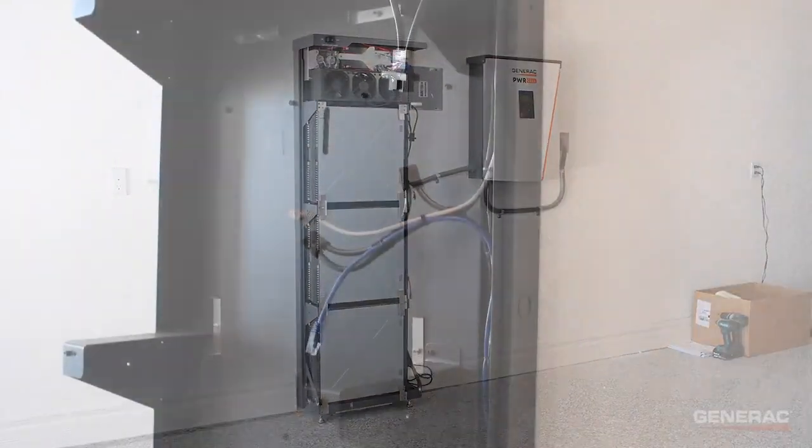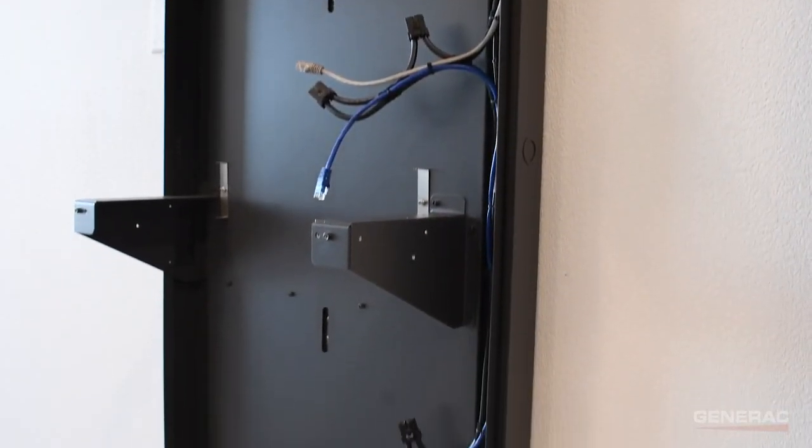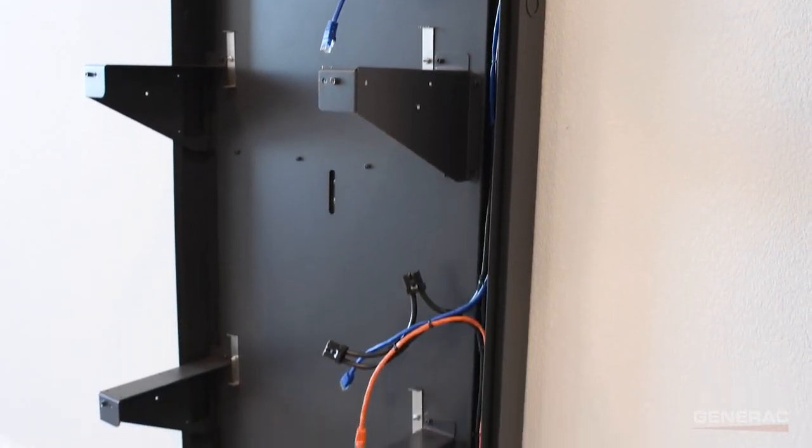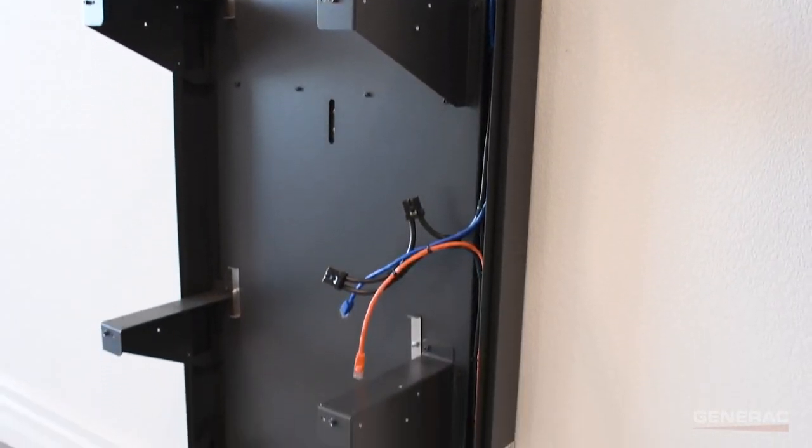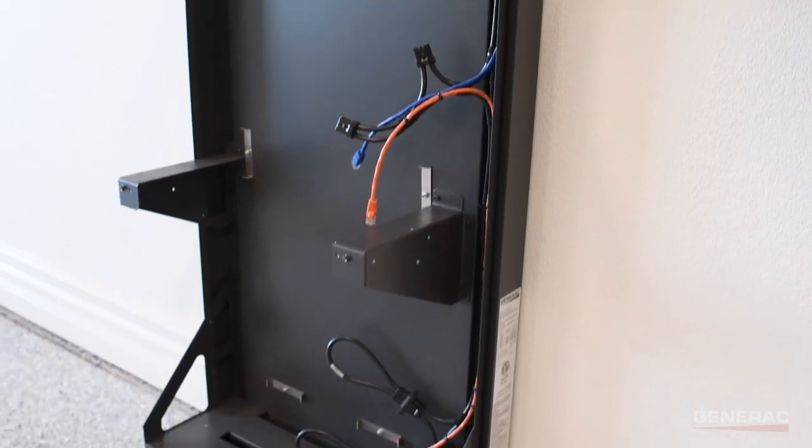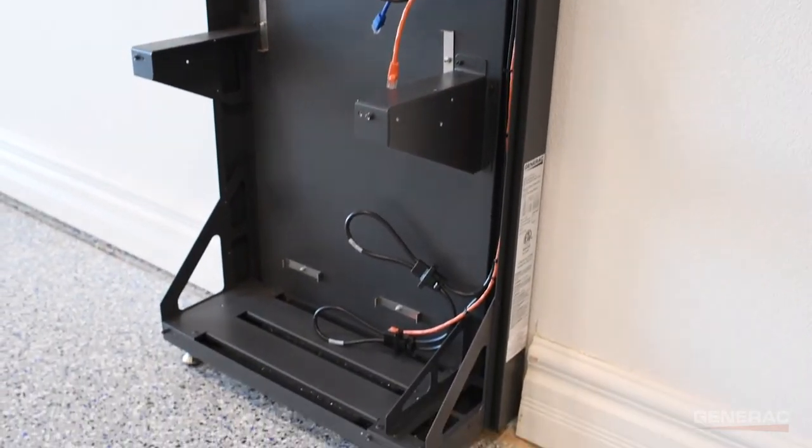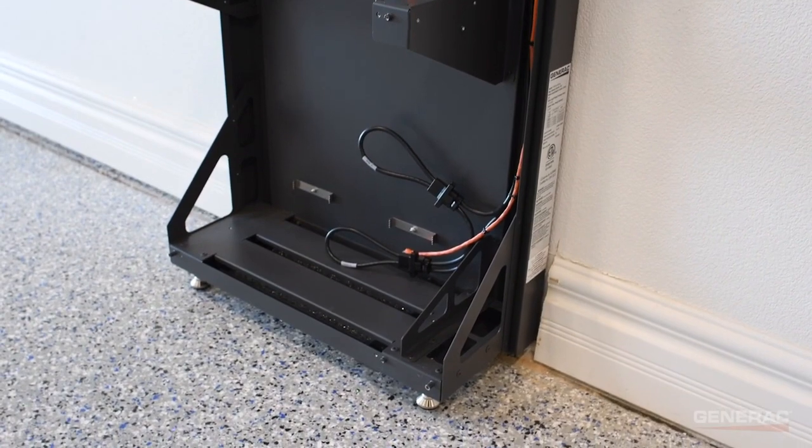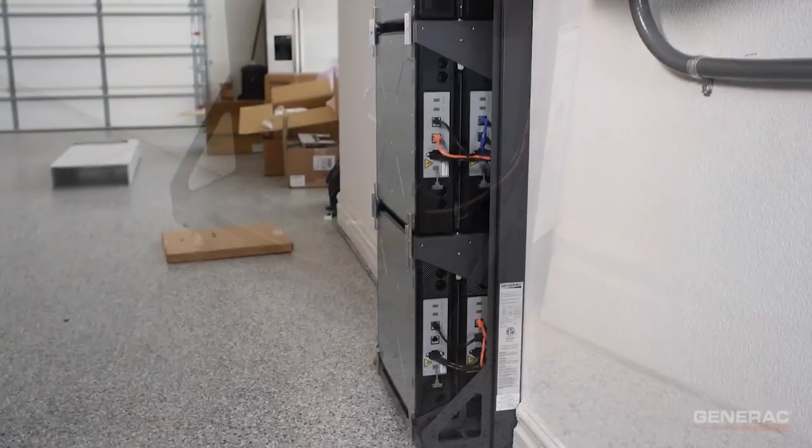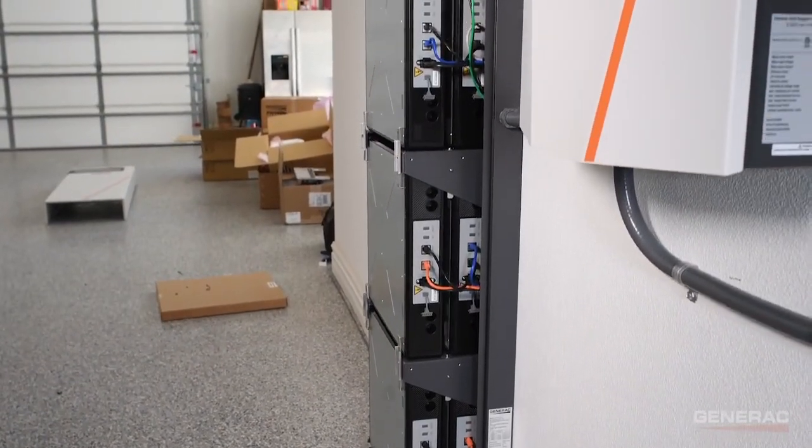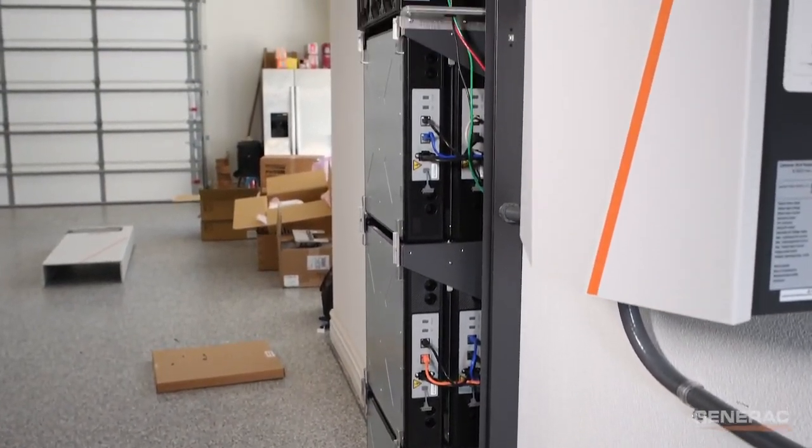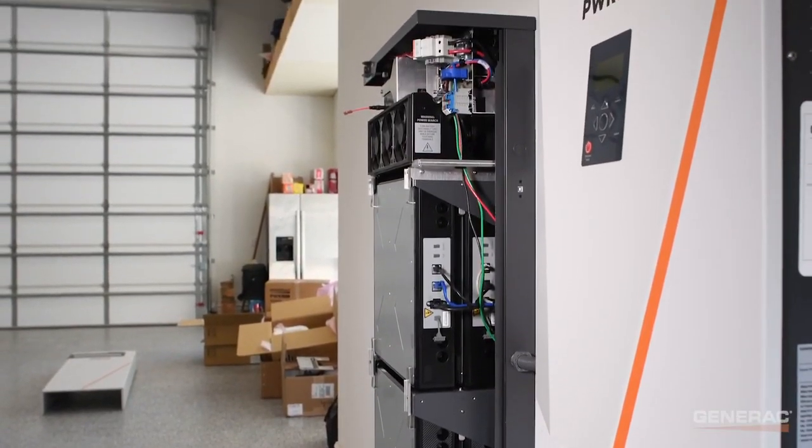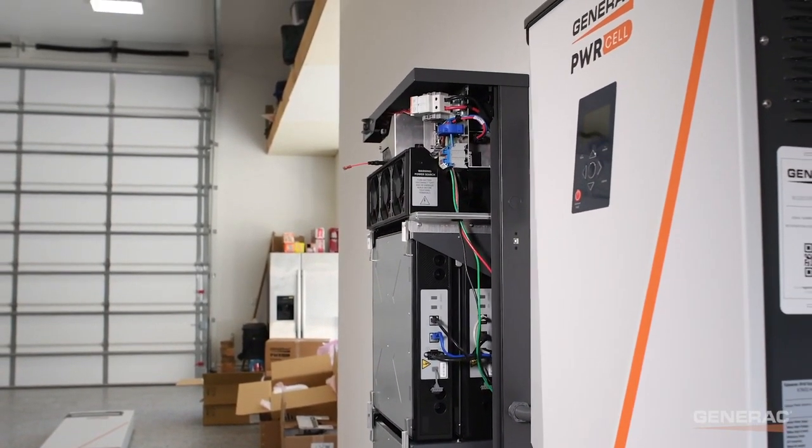Locate the battery's power cable harness. It's built into the battery cabinet and runs down the right side of the cabinet alongside the battery modules. It includes touch-safe power connectors that connect all battery modules in a series circuit to the BMU for charging and discharging, along with Ethernet communication cables that allow the BMU to communicate with each battery module.